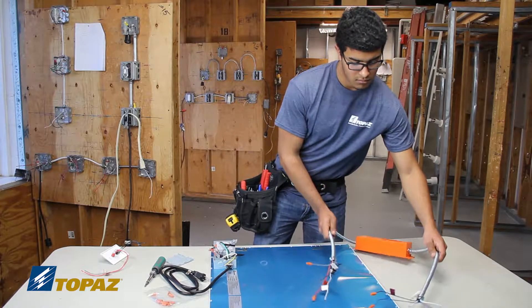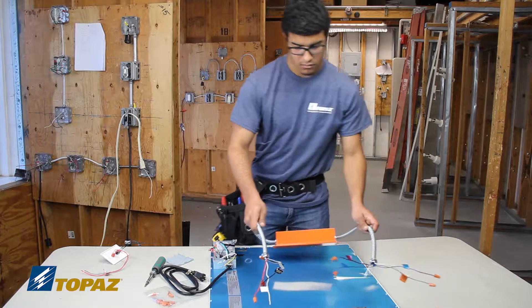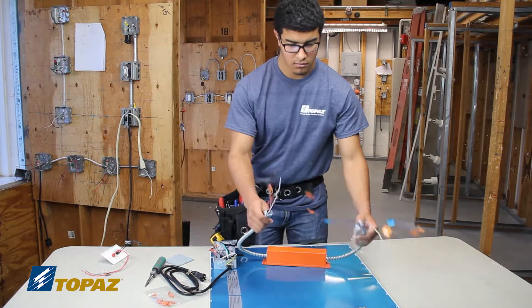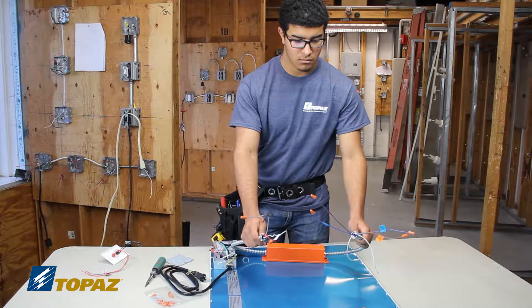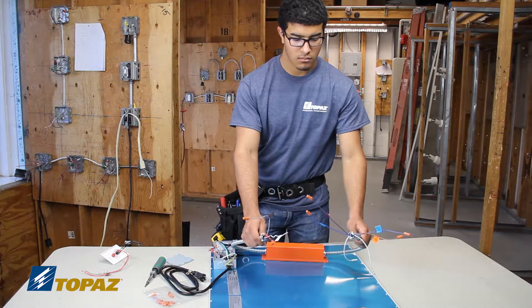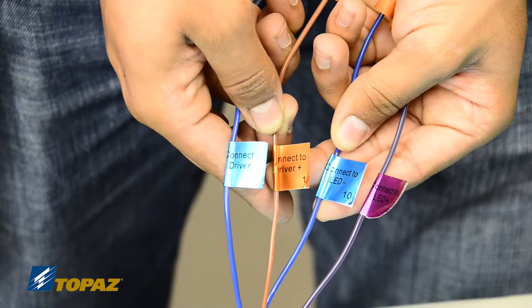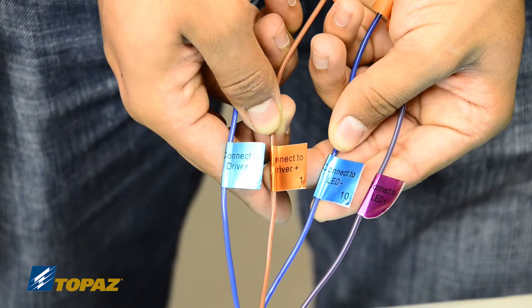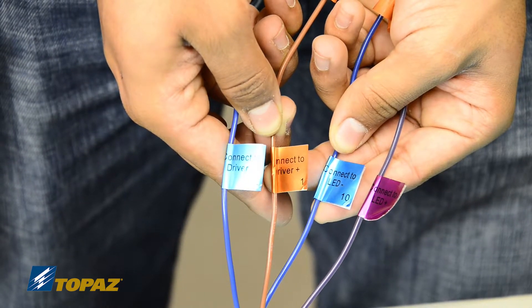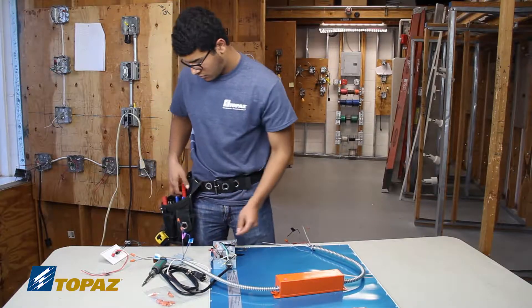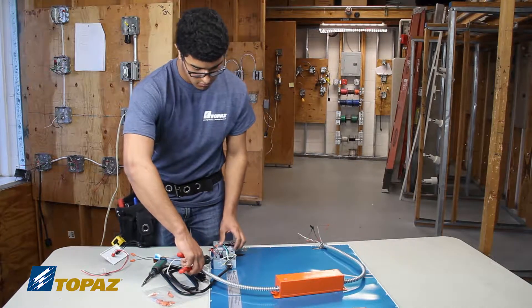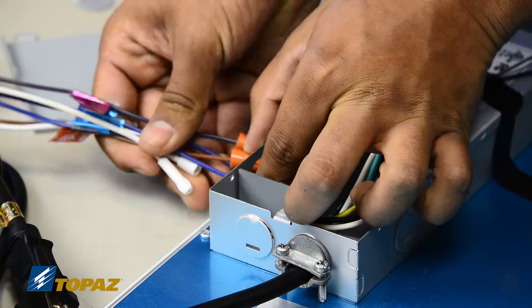The next step is to go ahead and pick up your emergency ballast, making sure you identify both ends. You have the one end which is going to be wired into the line voltage compartment and one for the low voltage. We will be starting with the low voltage, so you'll see that it's identified with the tags that say LED driver. You'll need to remove the knockout on the side of the junction box.